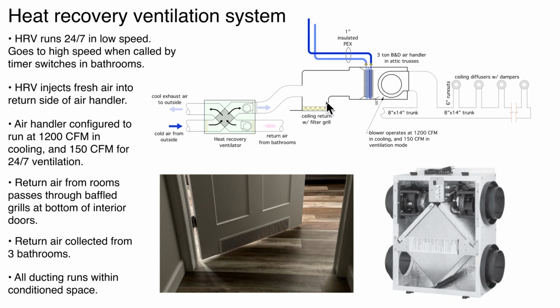And then rather than create an entire return air duct system, we use these in the doors. These are a product from Tamarack Technologies. Basically, you cut the bottom of the interior doors, you slide this up, and a couple screws hold it in place. This provides light separation and acoustic separation, but if the door of that room is closed, it allows air to come through without building a substantial back pressure on the system.